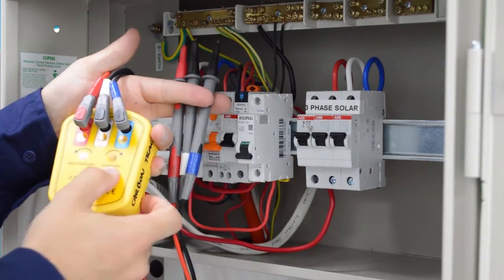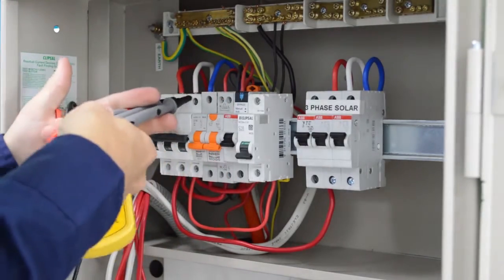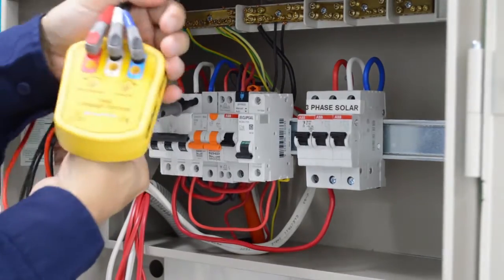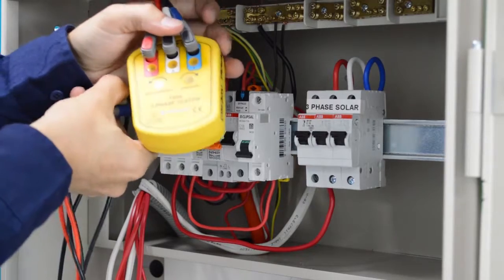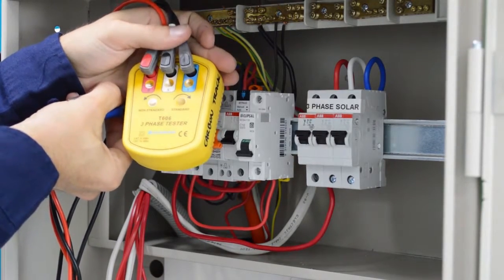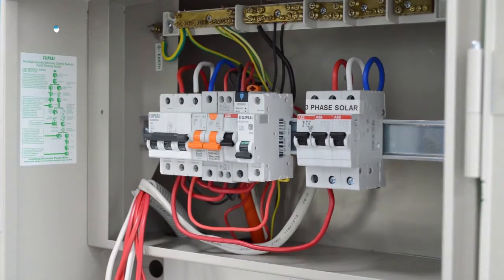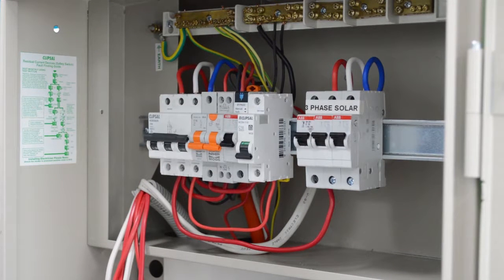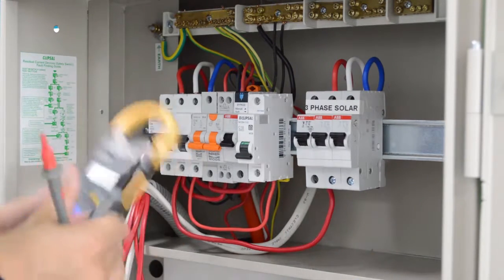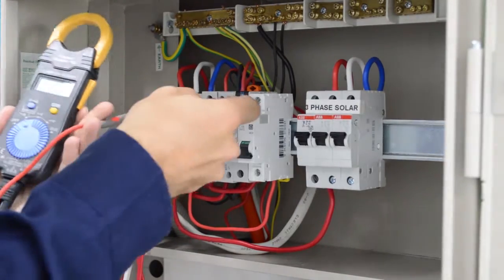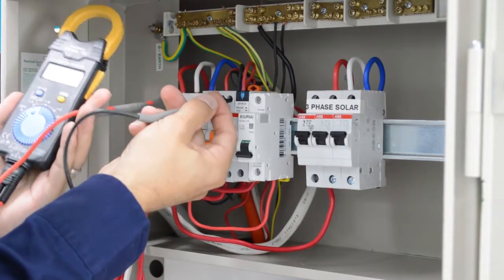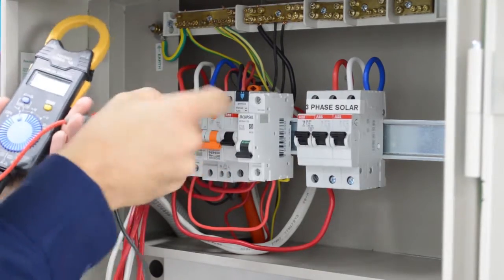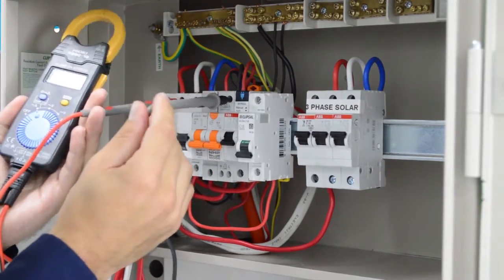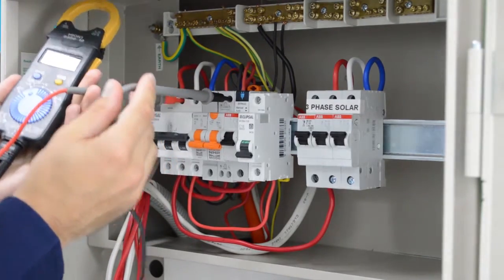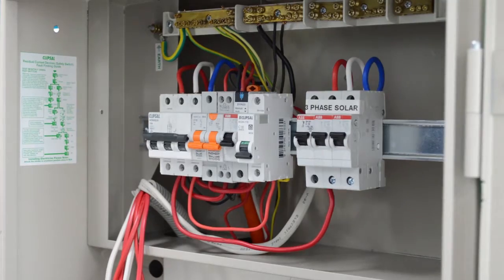Using a phase rotation meter, identify whether the phase rotation is standard or non-standard. As this is a demo board and there's no voltage present, I'm going to take this to be a standard phase rotation for the purpose of this installation. Now, in order to correctly identify which phase the breaker is, it is suggested that you use a multimeter to determine the phase, and you should be looking for 0 potential between the correct phase active on the main switch and the correct active on the circuit breaker you're connecting to. This will be important later on for current clamp connection.